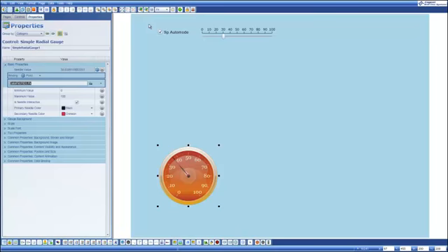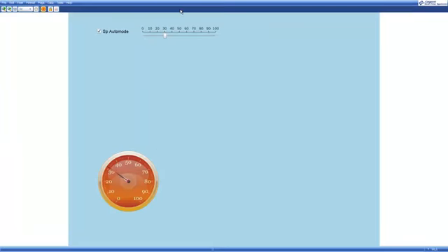And so I'm just going to go into run mode here and confirm that all of that is working. I should see my set point jumping around every 5 seconds. If I turn off auto mode, it stabilizes and I can manually drag it around, and as I do that I can see that my PV value is running correctly. So that looks good so far.